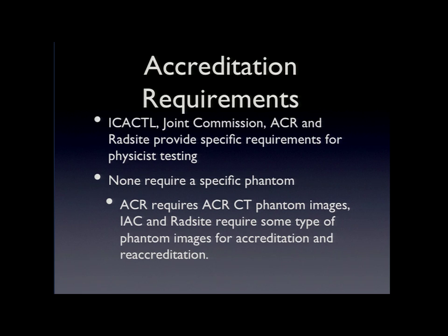So as far as accreditation requirements, Tyler is really going to go more into that, but I just wanted to touch base with it. There are right now 4 that are approved by CMS. It's more of a reimbursement thing that's driving it. But as far as their standards, none of them require a specific phantom be used for QC or for the evaluation. The ACR does require that you use the ACR CT Phantom to submit images for the accreditation process, but that's just done when you accredit, and then when you re-accredit every 3 years.